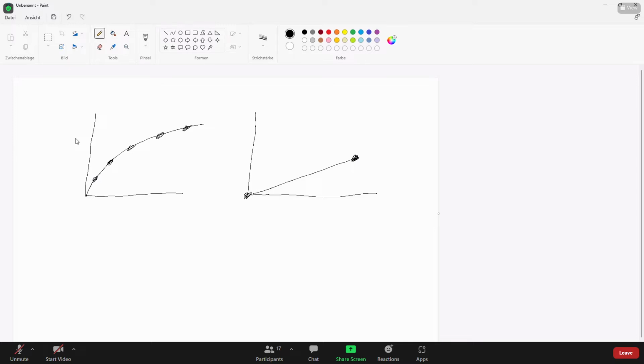And that means less points means you need not so much calibration standards. And especially when you work in the field of, let me say, analytics, where you have a particle size analysis also, or gas analysis, where the standard what you give on is lost after the calibration.